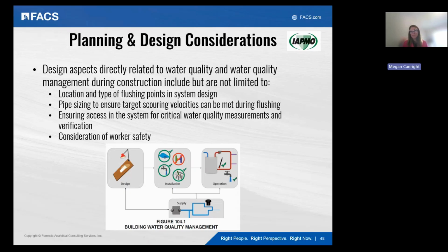I can't tell you how many times I've gone into a building and tried to sample the hot water return, and there's no hose bib or sampling point where domestic hot water return water can actually be sampled. The team can also make recommendations about pipe sizing to ensure pipes are sized appropriately for occupancy, avoiding too much water sitting stagnant, while still achieving enough velocity during flushing to move water through the building.